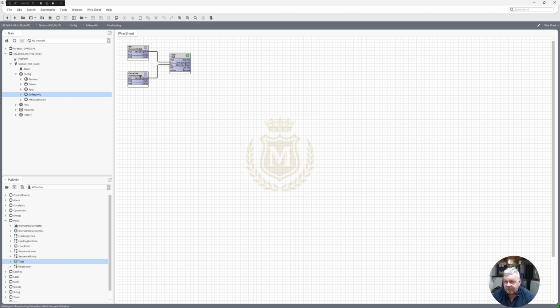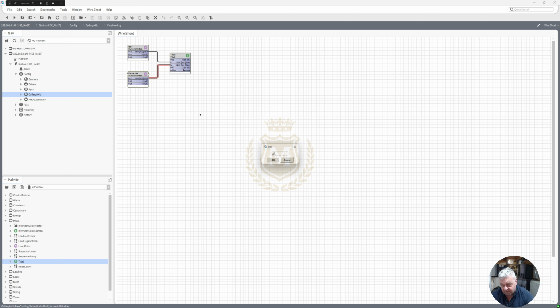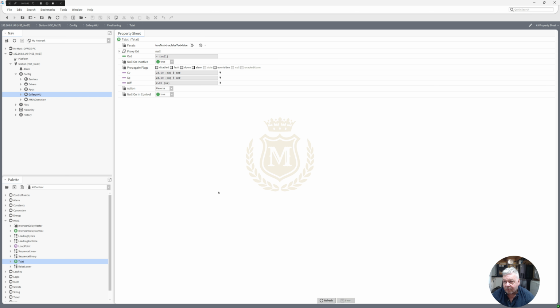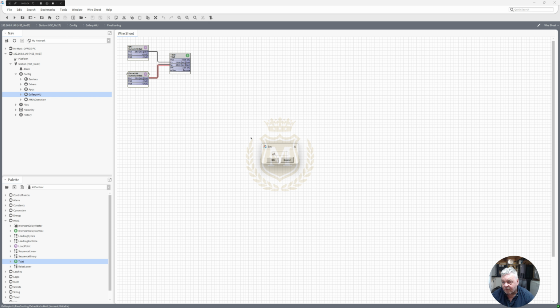So that's at 23, that's at 26. If I drop that down, actions, set that to 21, we've got a false there. So we've got the extract air lower than the outside air, so we can't do any cooling. Actions, set that to 23, and we shouldn't be able to do any cooling still. It's gone to a null there, so let's put that to false. Then we'll set that to 24, and we've got a true, because the extract air is 1 degree higher than that.